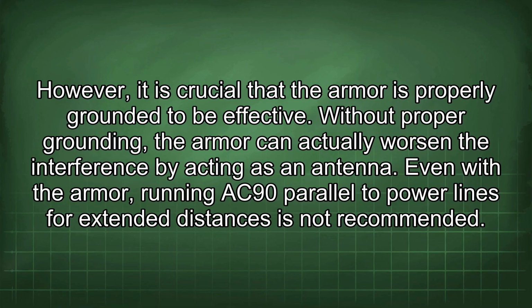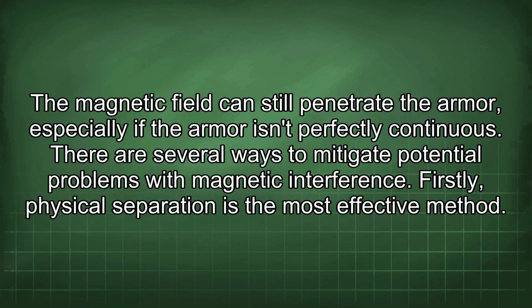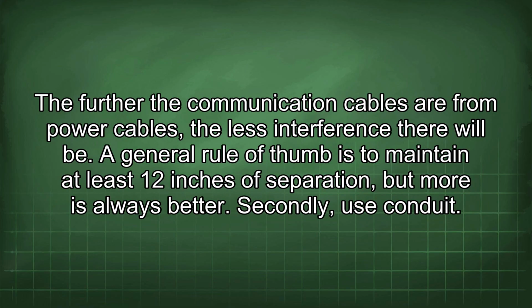Even with the armor, running AC90 parallel to power lines for extended distances is not recommended. The magnetic field can still penetrate the armor, especially if the armor isn't perfectly continuous. There are several ways to mitigate potential problems with magnetic interference. Firstly, physical separation is the most effective method. The further the communication cables are from power cables, the less interference there will be.